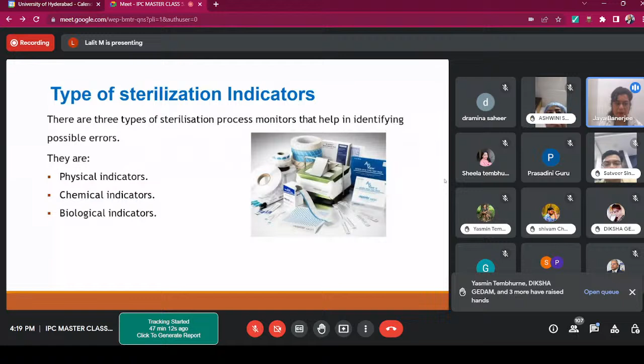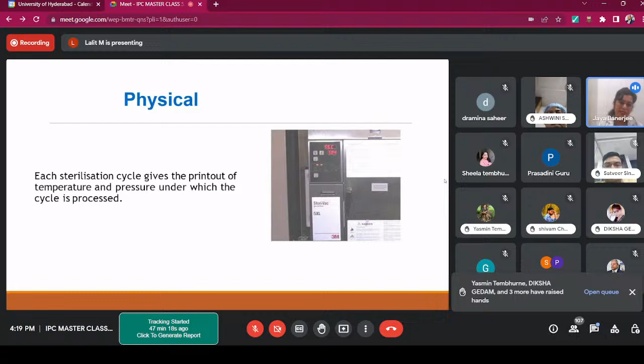Sterilization indicators are physical, chemical, and biological. The physical indicators are temperature and pressure. Chemical includes the Bowie-Dick tests and the process indicators. These are the biological indicators we must use for all implants and whenever required, particularly for the plasma sterilizer. In each load we have to use them.